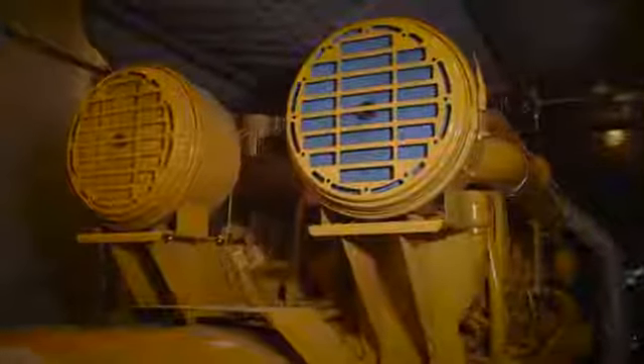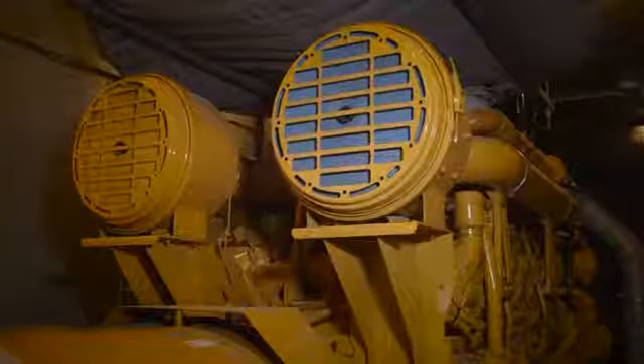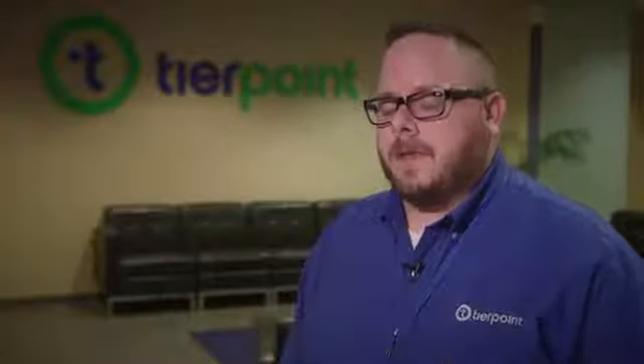What happens is utility will drop and our 1.1 megawatt UPSs will actually pick up the load, holding that load until our 2.5 megawatt CAT generators actually pick up the load from there. We have the ability to make that happen utilizing our paralleling switchgear.